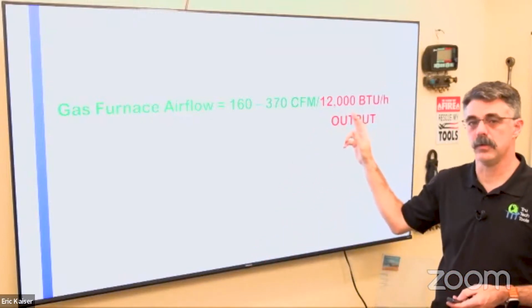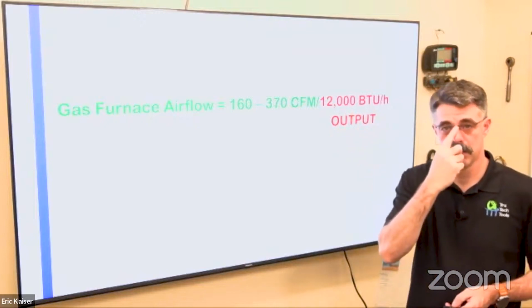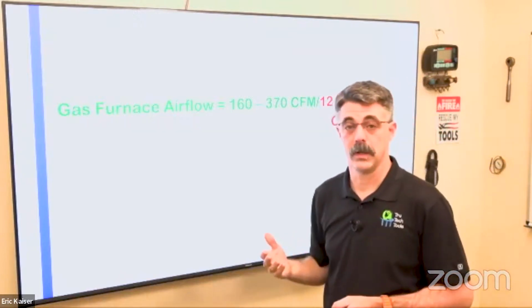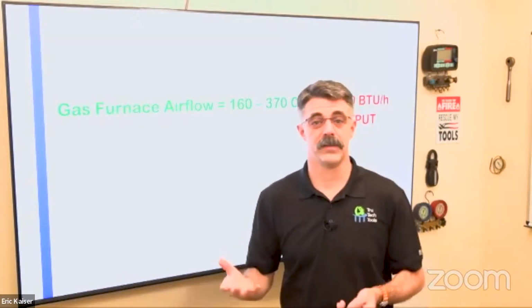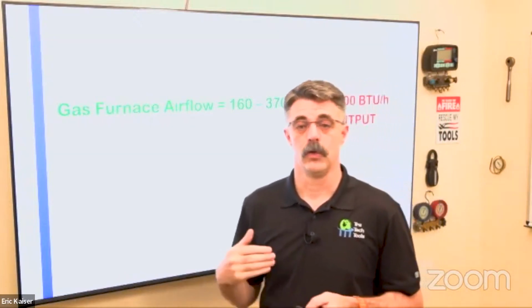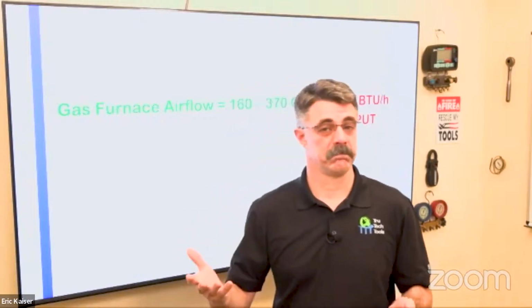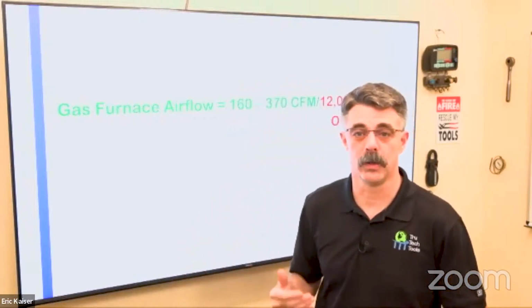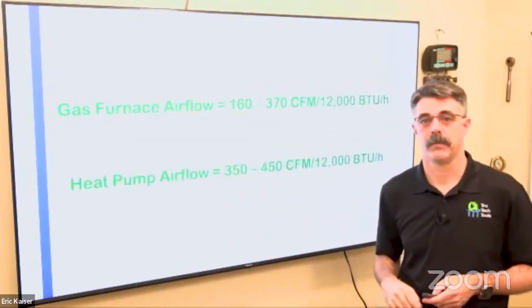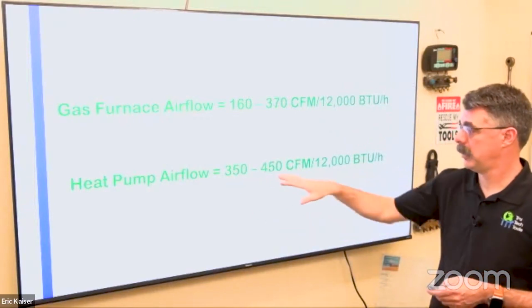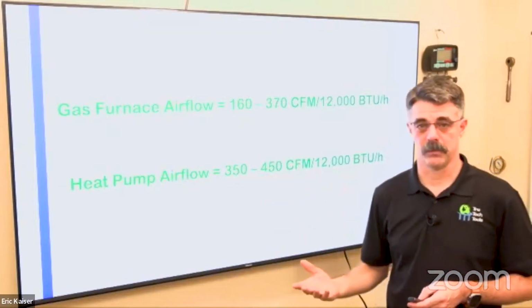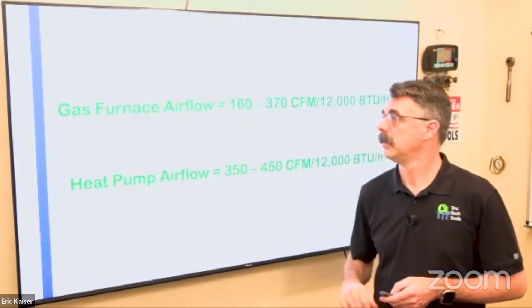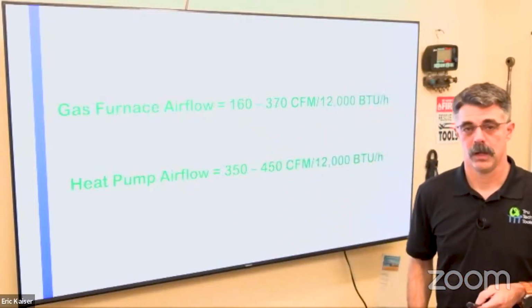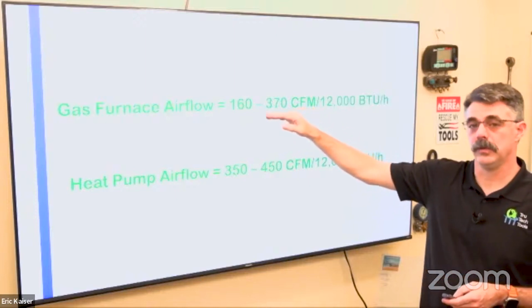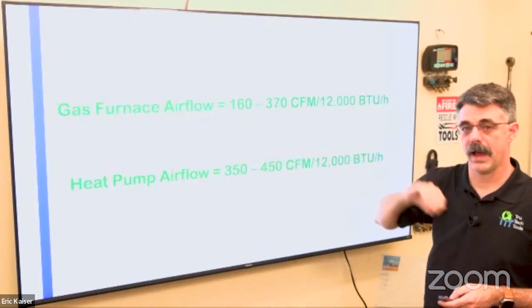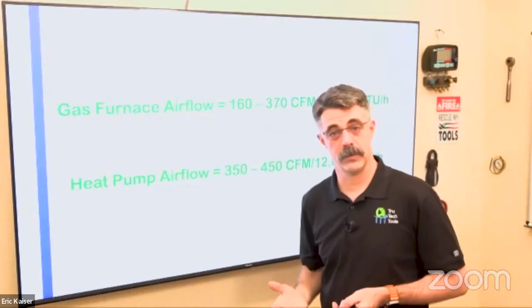So per BTU, our airflow is higher with a heat pump, right? Which means the temperature is going to be lower. The intensity of that heat coming out of it is going to be lower. So if it blows directly on a human, they're going to feel like they're getting cooler air blown on them, right? So heat pump airflow, 350 to 450 per 12,000 BTUs. That's a nominal, but that's the difference between the two. So you can see if we need the same BTUs from a heat pump that we had coming out of a gas furnace, we may have to do something with the ducts.